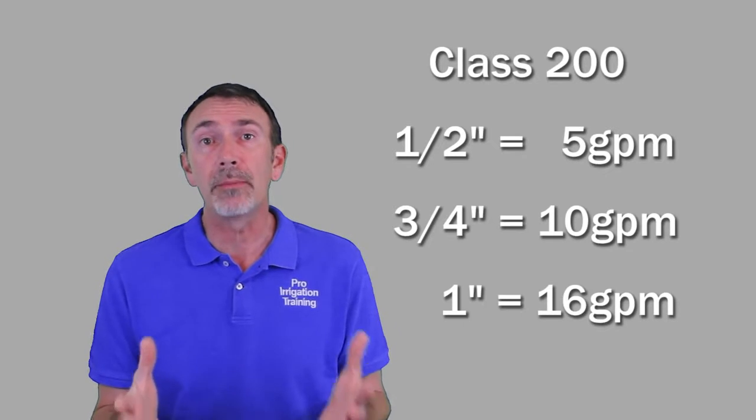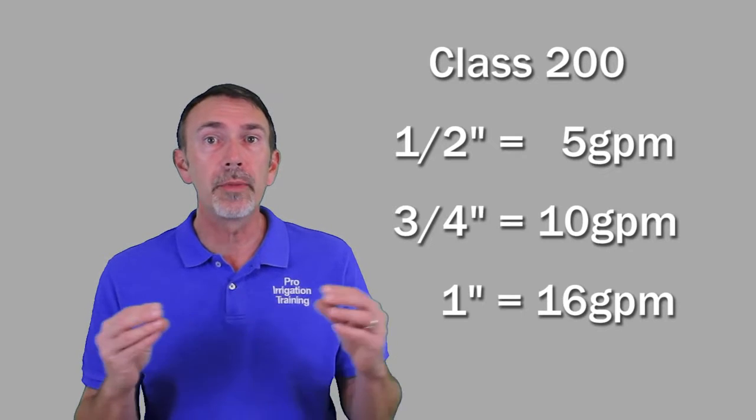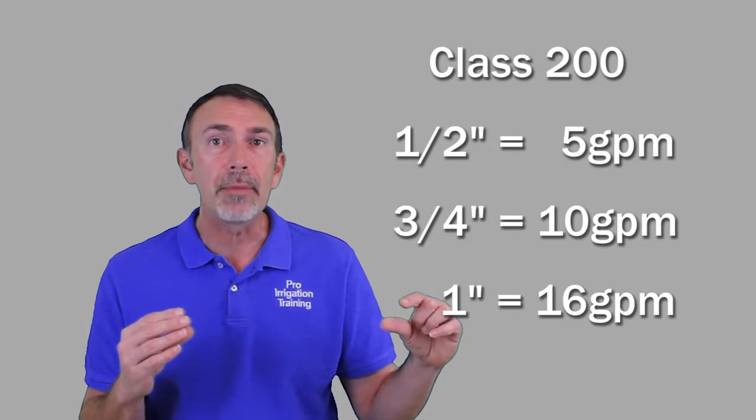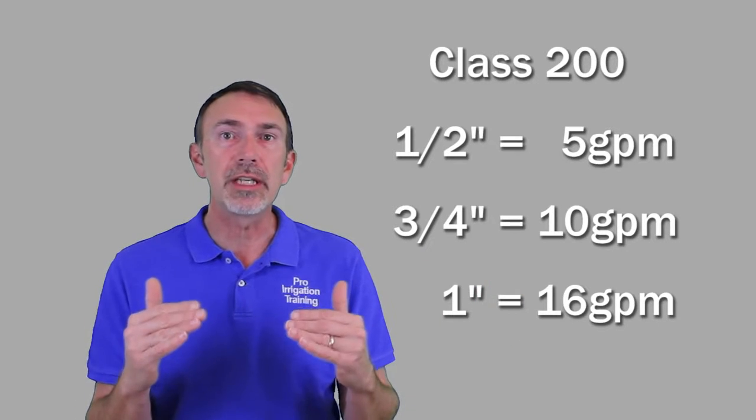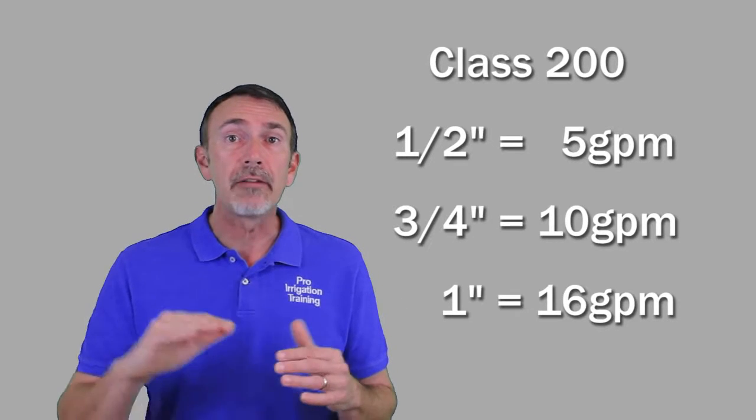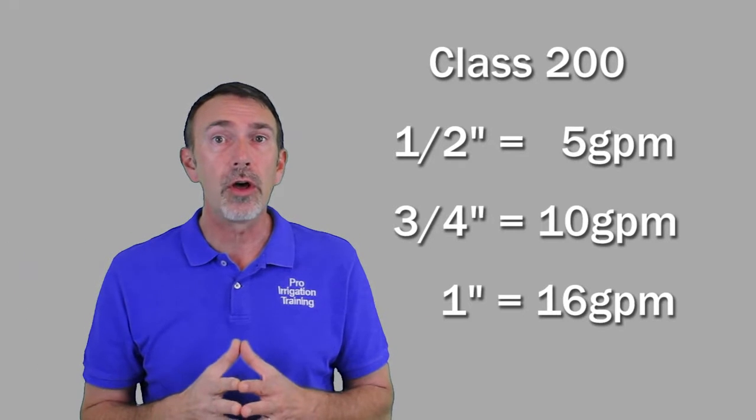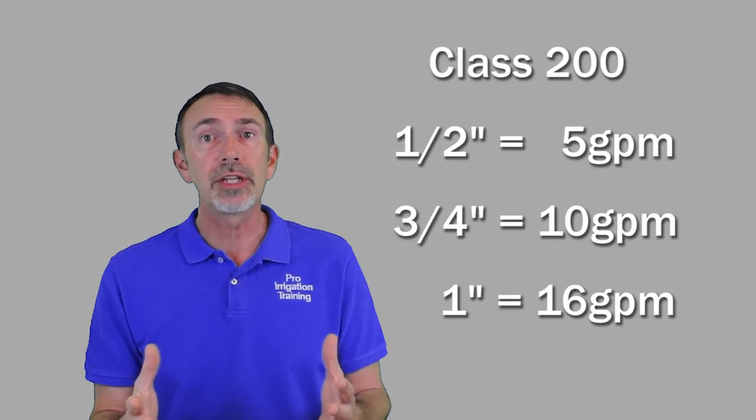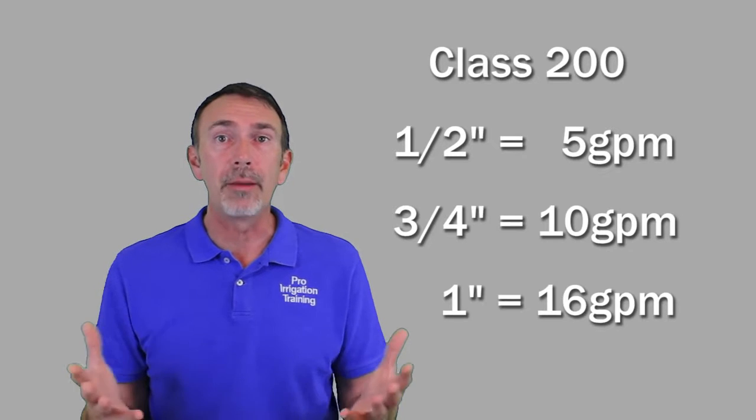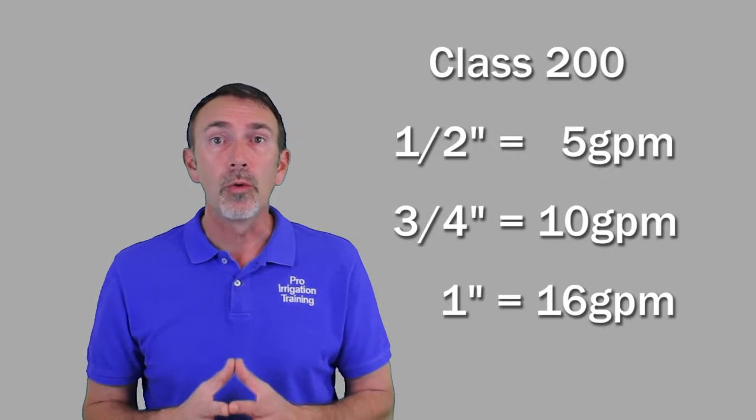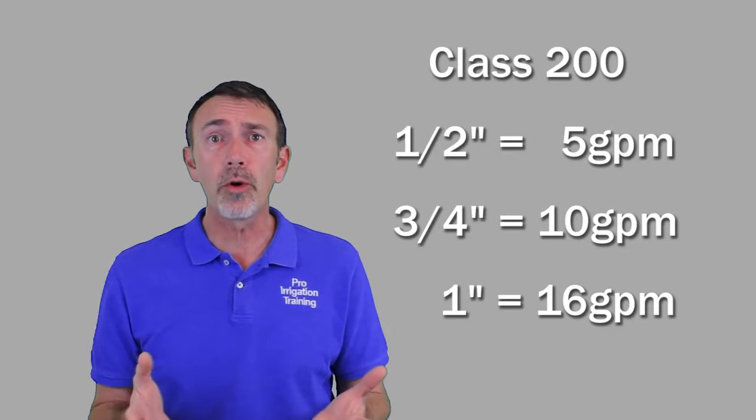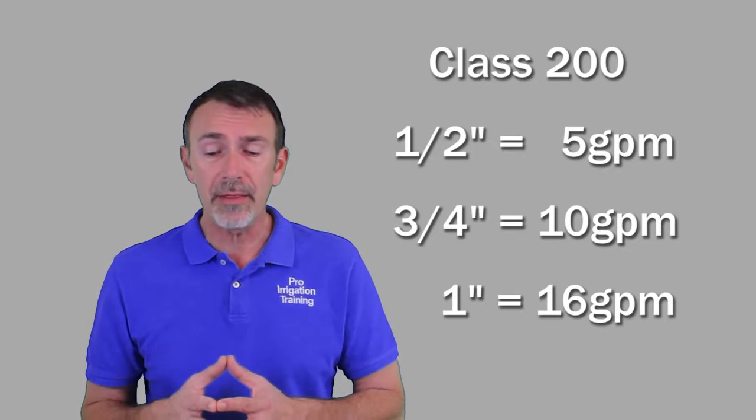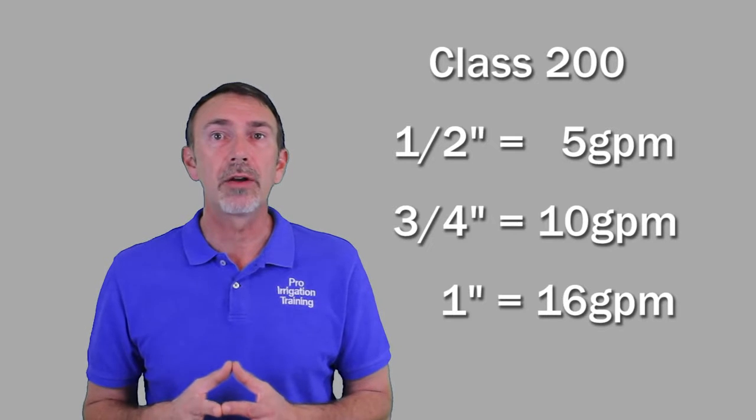It's not the maximum amount that the pipe can carry, but it's the maximum amount before friction loss—or the turbulence and the loss of pressure inside the pipe because of the water traveling through the pipe. We want to keep that at a certain speed. The faster it gets, exponentially the rate of friction loss starts to increase. So the half inch, we're going to have a five gallon per minute limit. If we go up to three quarter inch pipe, 10 gallons per minute is our limit. And when we get to one inch, 16 gallons per minute is our limit there.